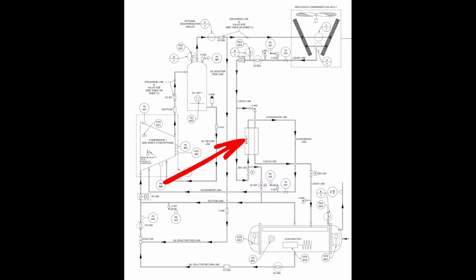It's just to maintain velocity and flow through the compressor at unloaded conditions, specifically low load conditions with low ambient conditions, right? We've got lower head pressures due to low ambience and low load conditions, so we've got to be careful, because if we don't maintain the velocity correctly, we lose the ability to control oil. Oil flow and oil return back to the compressor, our oil management side of the system, begins to fall apart in those situations. That is why they have the VI option available, so that in low ambience with low loads we're able to maintain oil control, and that's what gets a lot of machines in trouble.